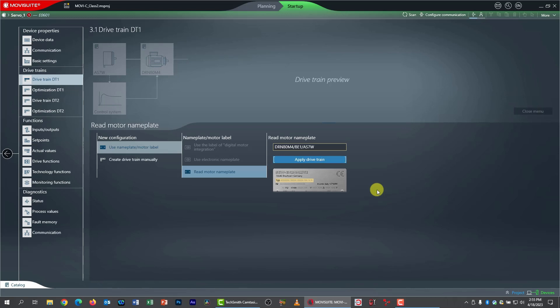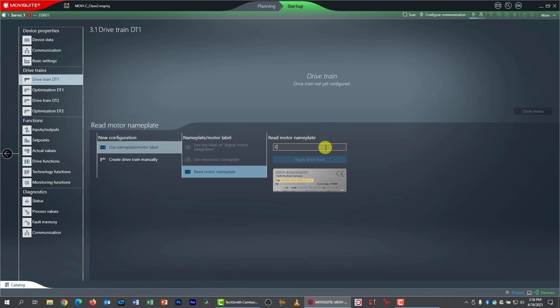I am not going to key in the temperature sensor information or the encoder. Neither one is accessible with that cable disconnected. If I say that either one's there, it's going to just start throwing up continuous faults.